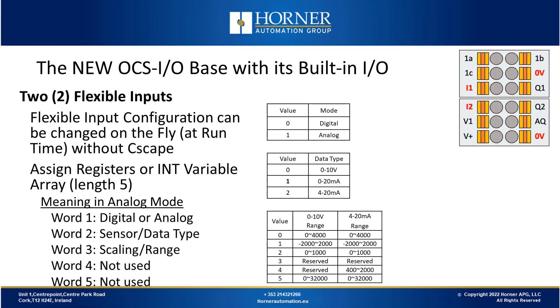Another thing that adds to the flexibility of these inputs is you can change how the inputs are configured — as either digital or analog, and what the ranges are — without hard-coding that into Cscape. You can assign variables or registers to that function and do it in the field. For example, you could build your own maintenance screen to change the configuration of those flexible inputs, useful where sometimes you want to use a voltage sensor and sometimes a current sensor.